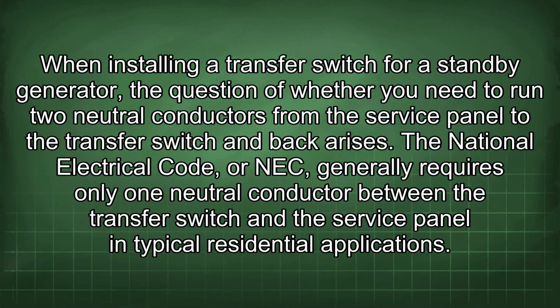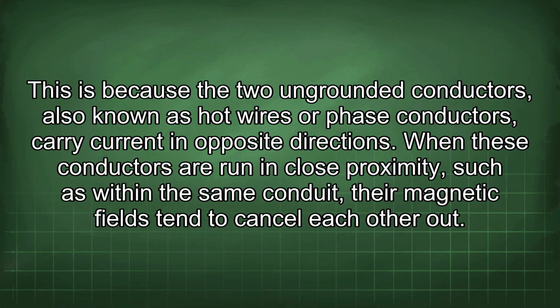When installing a transfer switch for a standby generator, the question of whether you need to run two neutral conductors from the service panel to the transfer switch and back arises. The National Electrical Code, or NEC, generally requires only one neutral conductor between the transfer switch and the service panel in typical residential applications. This is because the two ungrounded conductors, also known as hot wires or phase conductors, carry current in opposite directions. When these conductors are run in close proximity, such as within the same conduit, the magnetic fields tend to cancel each other out.